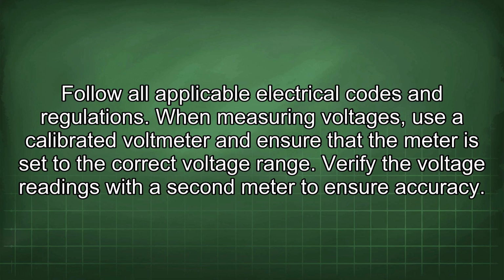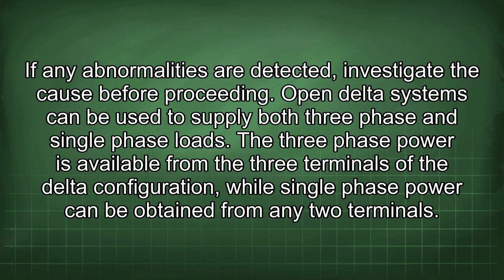When measuring voltages, use a calibrated voltmeter and ensure that the meter is set to the correct voltage range. Verify the voltage readings with a second meter to ensure accuracy. If any abnormalities are detected, investigate the cause before proceeding.